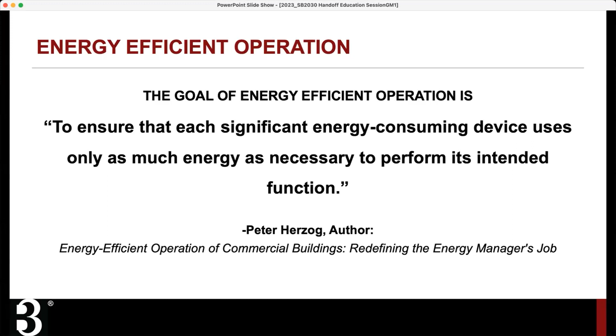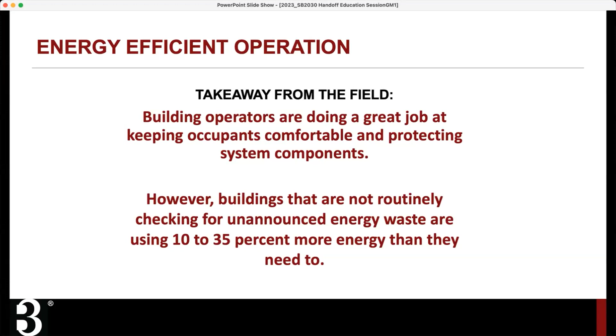In the field, we see that building operators do a good job keeping occupants comfortable and protecting system components - they handle belt changes, filter changes, etc. And if the building occupants are hot or cold, the building operator is going to hear about it. However, they don't typically routinely check for what we'd call hidden energy waste that doesn't make their phone ring. Buildings that are not routinely checking for this kind of unannounced energy waste are using 10 to 35% more energy than they need to.